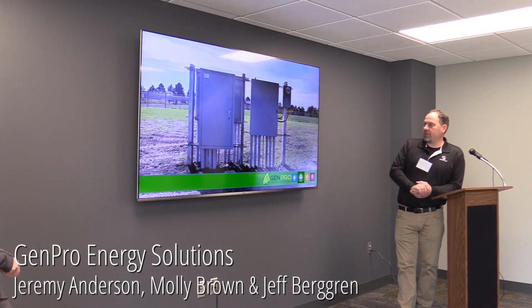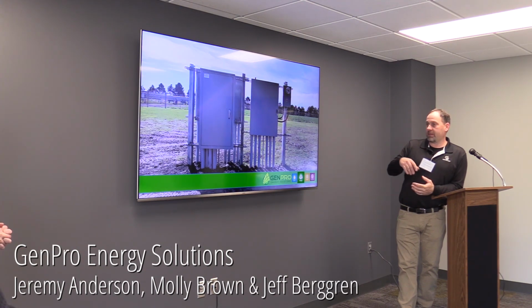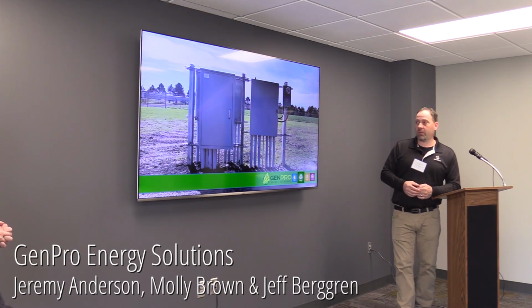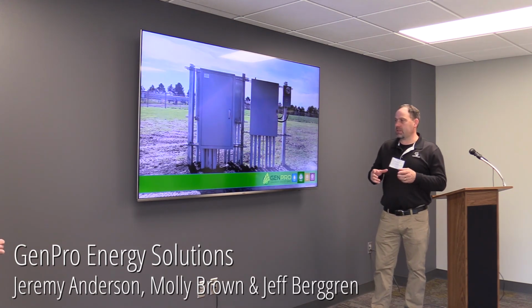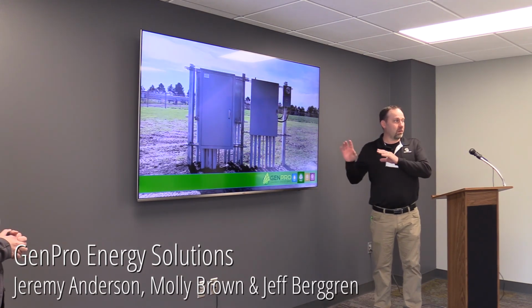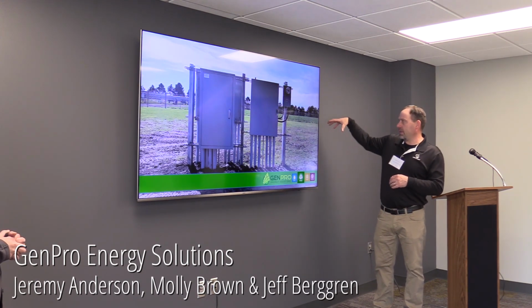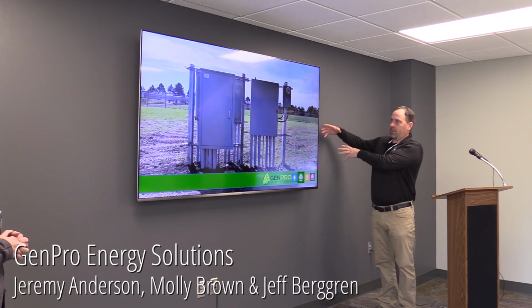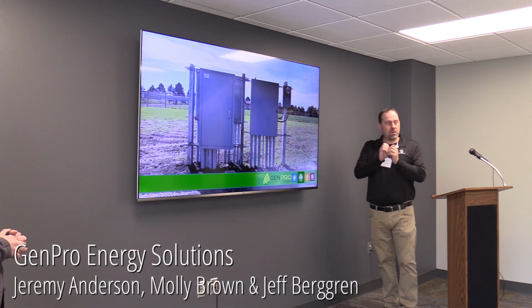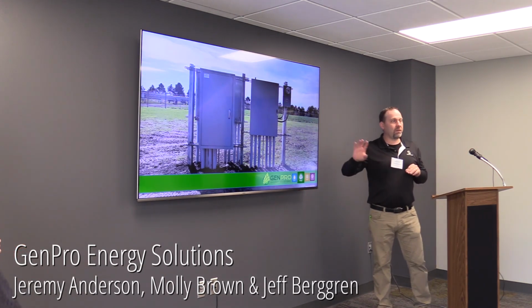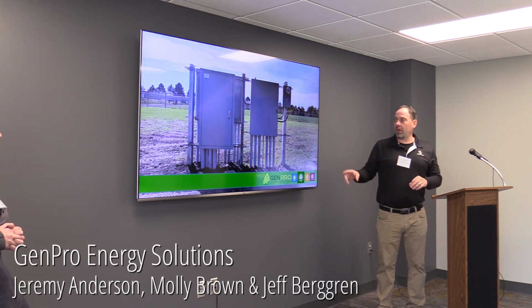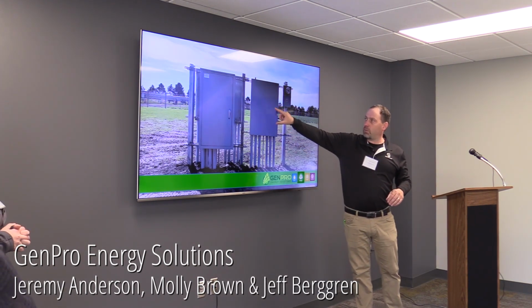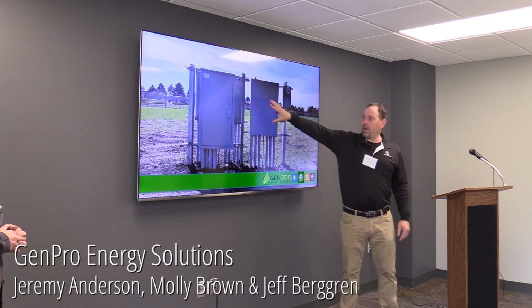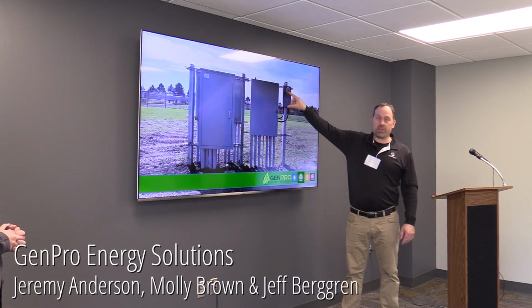So this is Aurora, and this is a very unique situation. This is part of the buy-sell program that Molly was talking about. NPPD has a specific way that they would like us to hook this up, and this kind of demonstrates how it is. You can't see the transformer, it's sitting right next to it here, but that transformer has two output feeds coming out of it. One output feed feeds the wastewater treatment facility, and the other output comes into this first box, which is what they call a CT box, and it meters all of the flow of electricity through this box and records it here in the meter.